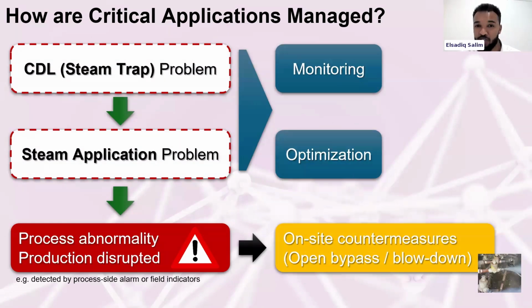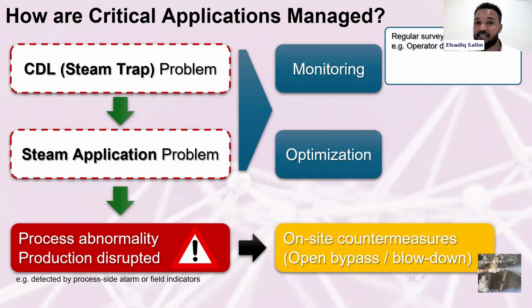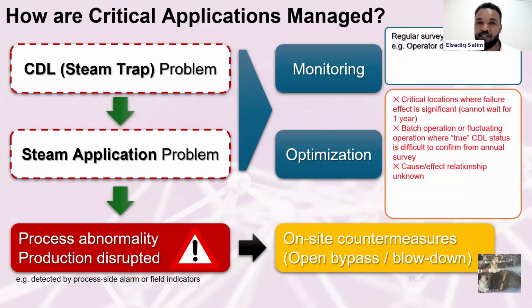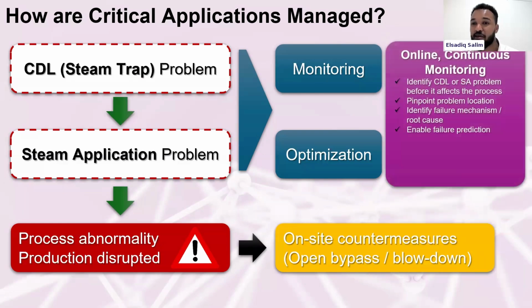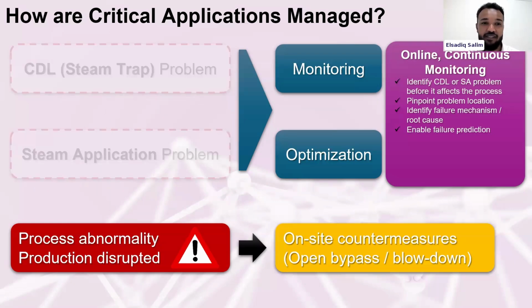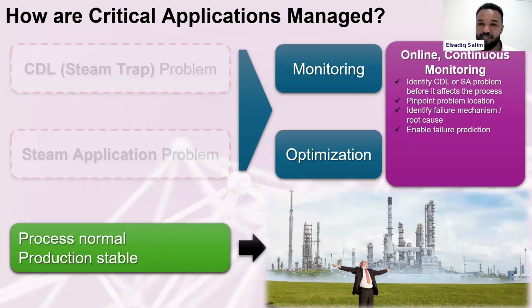And typical solutions are monitoring, as I've been talking about this whole presentation with regards to regular surveys. So you can monitor the steam traps annually. However, what you miss out on are these critical applications where you can't afford to leave it switched off or leaking for the full year. So the solution in this case is an upgrade onto continuous monitoring, which I'll just touch on briefly due to time. This is where you have basically a non-stop, continuous steam trap inspection device on critical locations. Not all of the steam traps on site, but areas you highlight to have a very high leakage cost, a very high emissions factor, or where they're attached to process heaters and process applications that you cannot afford to have shut down. And from this continuous monitoring, you are able to predict when those steam traps will fail so that you can prevent unplanned shutdowns. The general outcome is a very, very happy site and stable production.